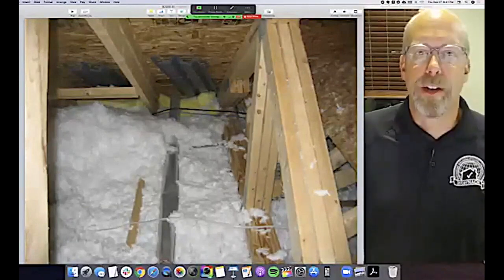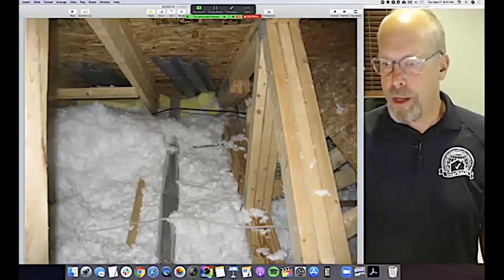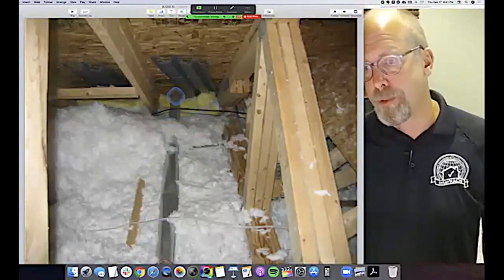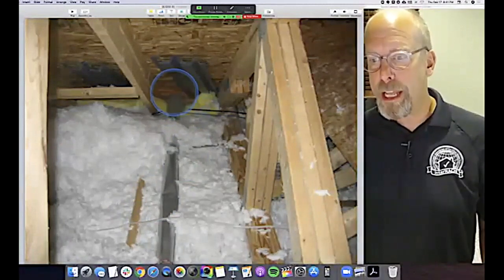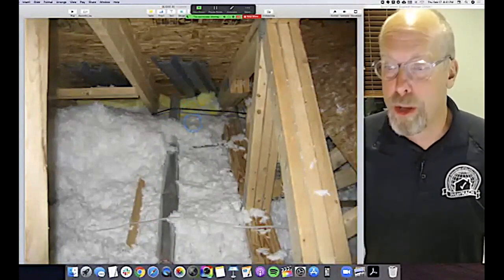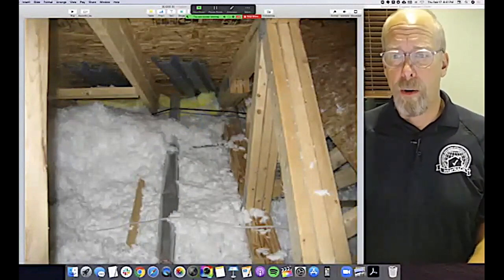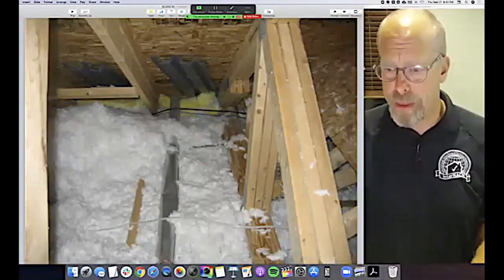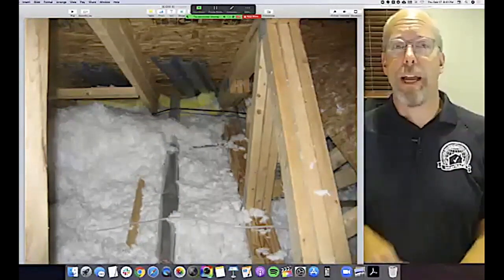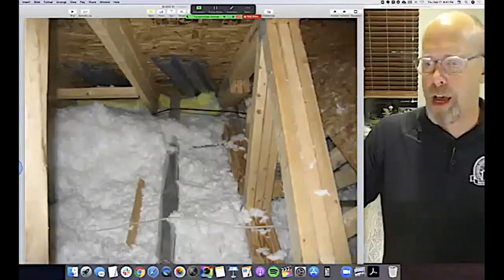It's the bathroom exhaust fan blowing into the attic. And it's blowing into the soffit, the soffit vent or the eaves area. It's right into the roof sheathing, actually. And according to modern code, I don't care when this house was built, all mechanical exhausts coming from the bath should exhaust to the outside. And this isn't the outside, that's roof sheathing, right? So we should be blowing this outside.